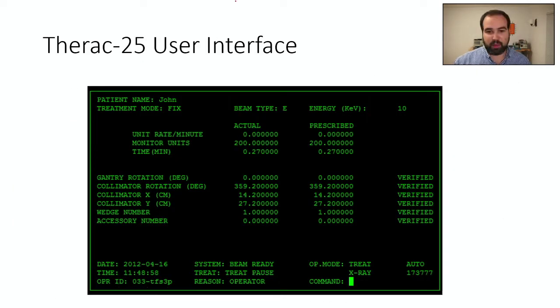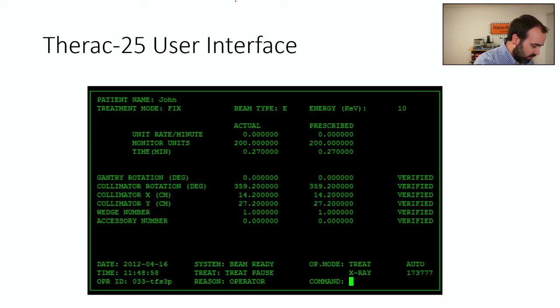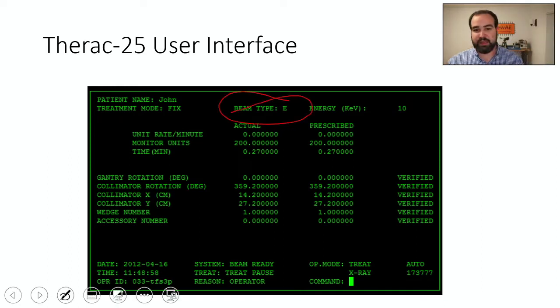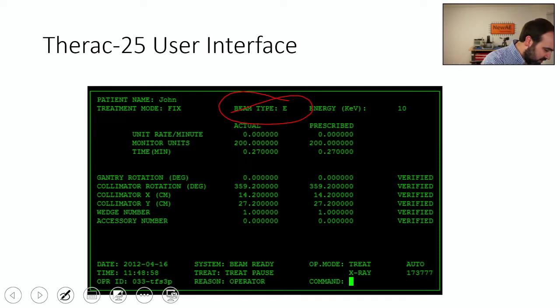The user interface was based on what would now be a quite old computer, but at the time it made sense. The operator would enter information such as the expected rate and the beam type — either an electron beam or an x-ray beam — just by entering 'e' or 'x' to switch between these modes, along with various other settings.